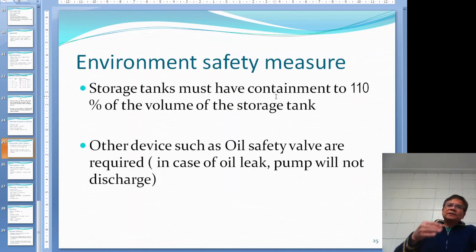Now, when you're burning oil, there are other safety devices too. One really common one in modern oil burning equipment is what they call the oil safety valve. In the steam safety valve, if you have too much steam, the safety valve blows, but the oil safety valve works exactly opposite.